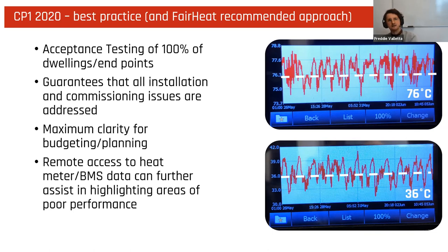It should be said, actually, that in my 4.5 years of acceptance testing at FairHeat, if we had taken this 10% plus 10% approach instead of the 100% approach from the outset, I don't think there would have been a scheme where we didn't actually end up testing 100% of dwellings. Results-wise, this 100% dwelling testing ensures that commissioning issues are not missed. Say, for example, these graphs on the right show return temperatures from two phases of a London development. The top graph shows return temperatures from the first phase, which didn't go through any testing at all. And the bottom graph shows the second phase, where 100% of those dwellings were acceptance tested. You can see there's a drastic difference between the return temperatures, showing that performance has actually been met in this phase.